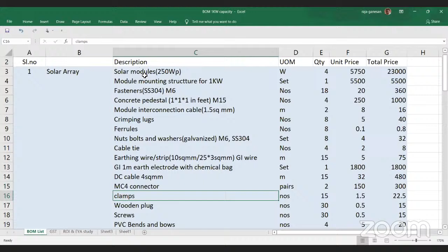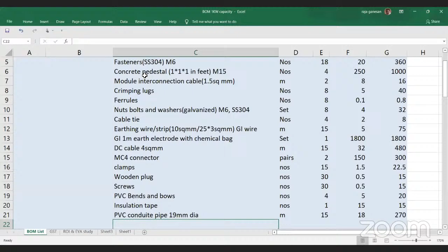Then the concrete pedestal size and grade, M15 grade concrete, is given. Then module interconnection cable, 1.5 square mm, is used. Then crimping lugs and ferrules to denote the numbering of the lines, nuts and bolts and washers in galvanized material with M6 size and SS304, cable ties, earthing wires, earth electrode, DC cable of 4 square mm, MC4 connector, clamp, wooden plug, screws, PVC bend, bows, insulation tape, and PVC pipe - all related to the PV array side.